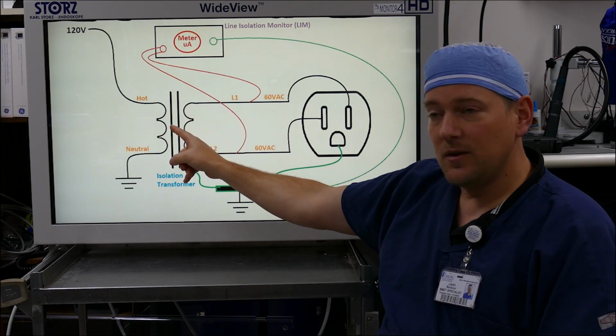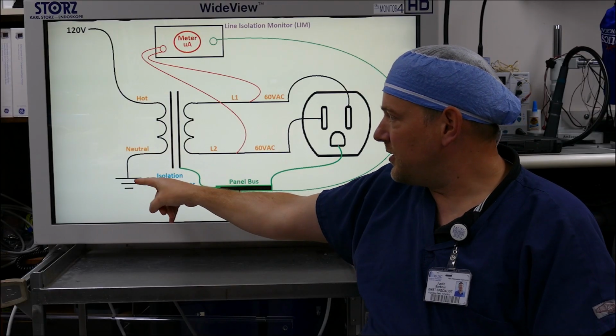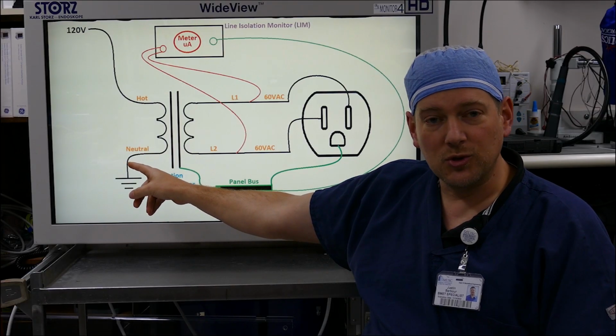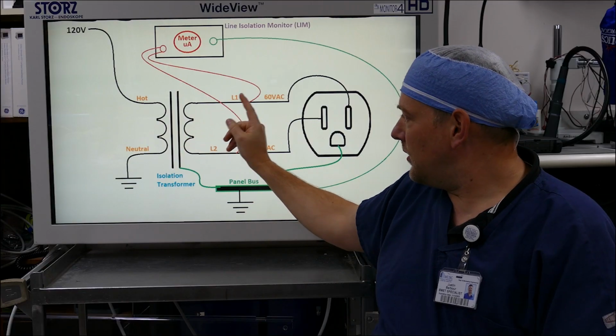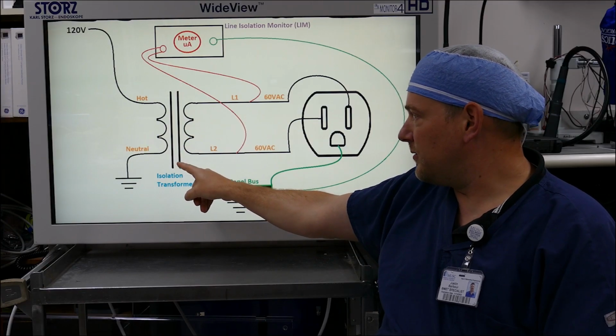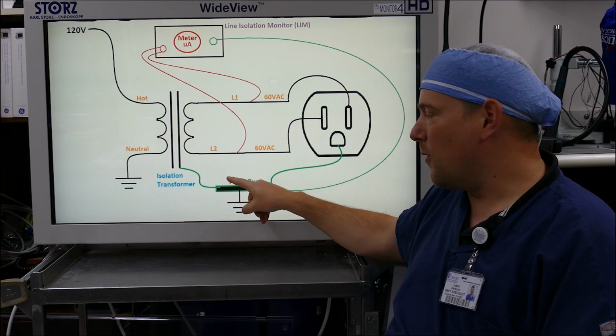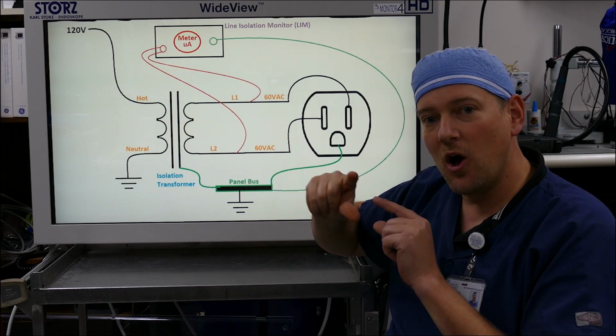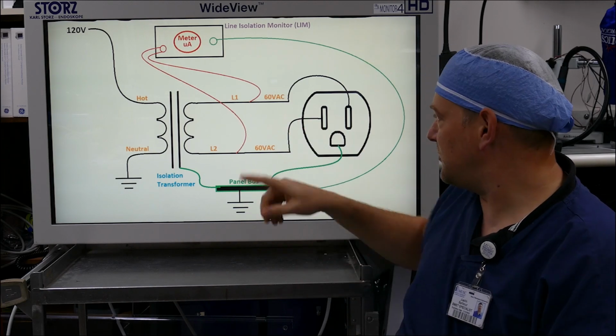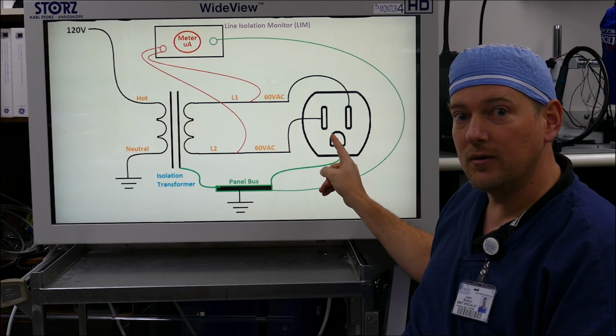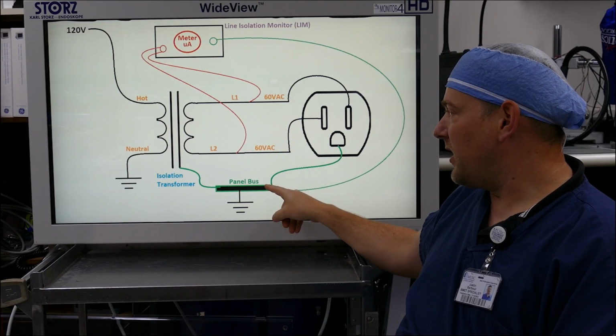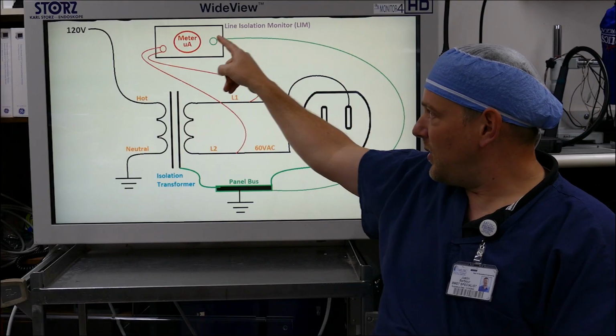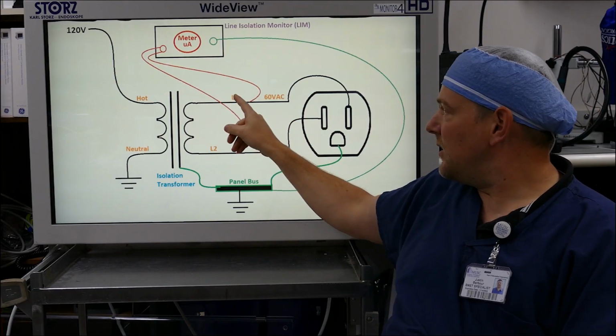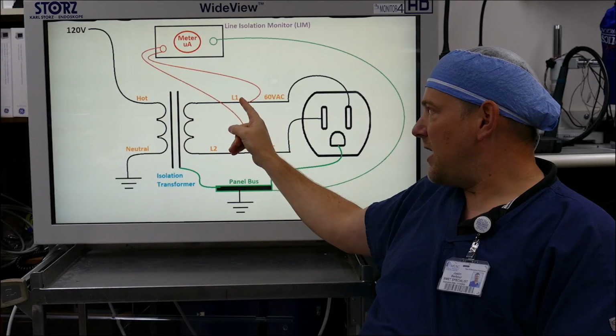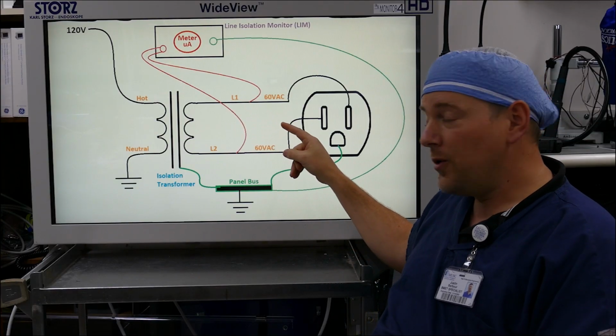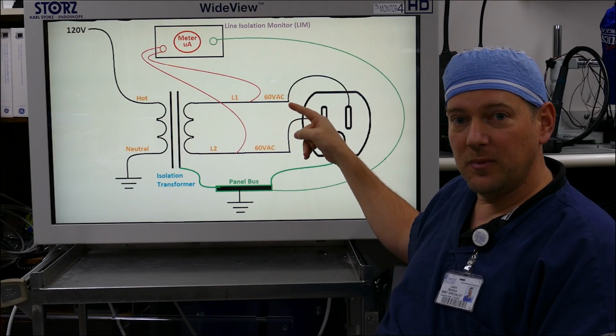120 volts comes into the primaries of the transformer. The other side of the transformer is at neutral potential. You have a ground that goes from the chassis of the transformer over to the panel bus. And it'll be a long copper strip of all your grounds to all the electrical outlets that are in your operating room. You'll also have one wire that goes from that panel bus all the way up to a meter. Over here on the secondaries, you'll have L1 and L2. Both of the secondaries will be at 60 volts potential.